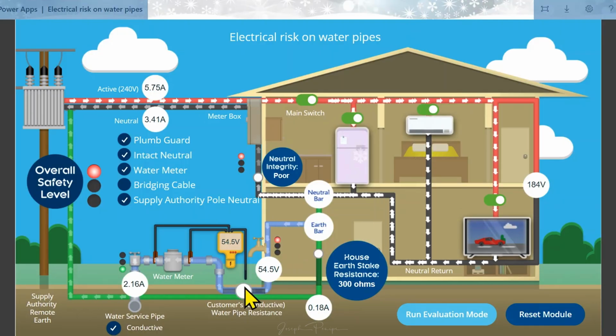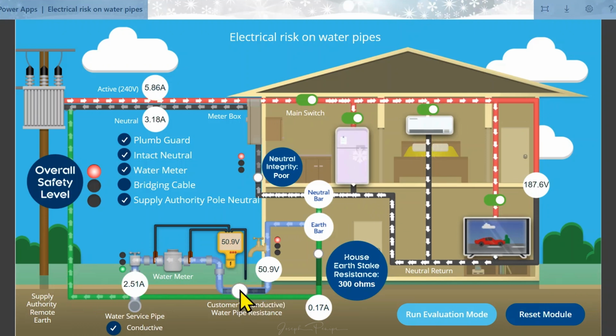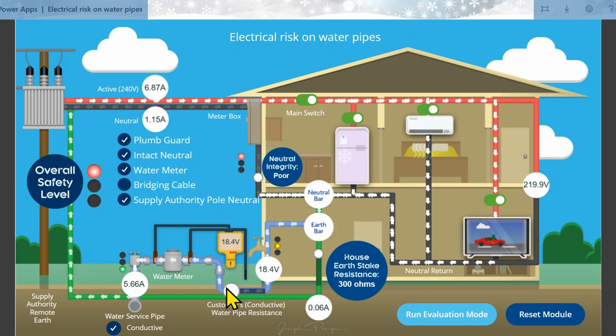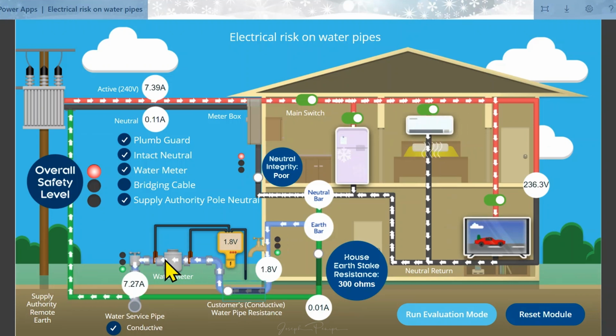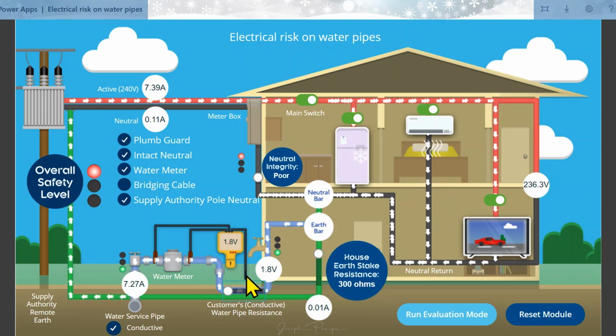The Plumb Guard does not have a visual display as that indicated on the simulation, but is designed to raise an audible and a visual alarm if it detects a voltage greater than 6 volts between either sides of the metallic surface that's being worked on across to the remote reference earth that's installed on site.